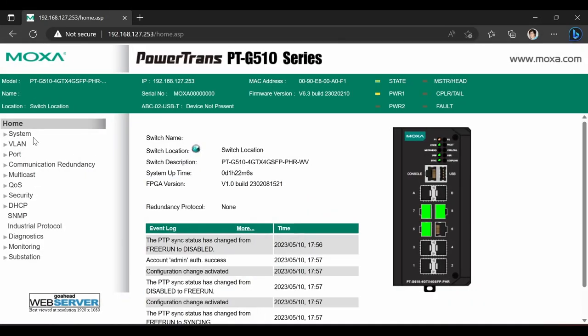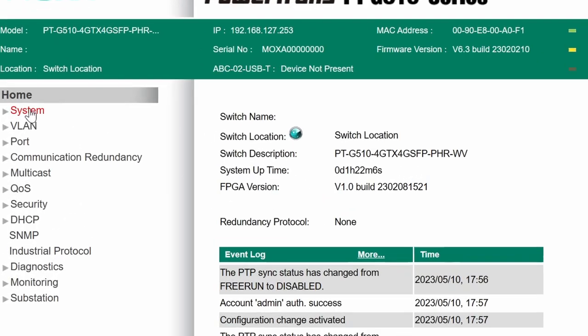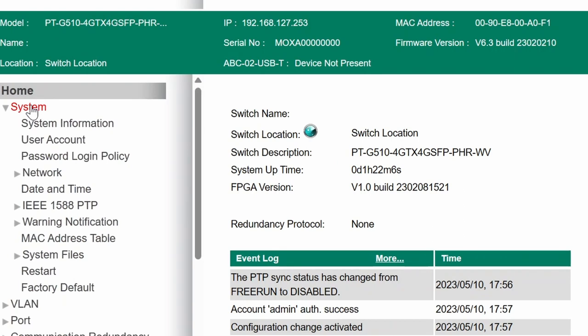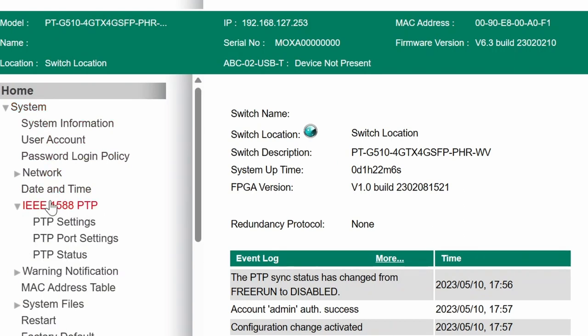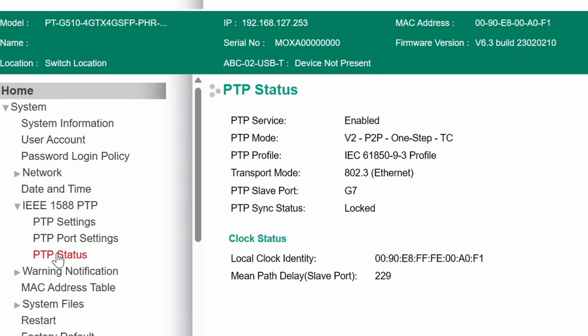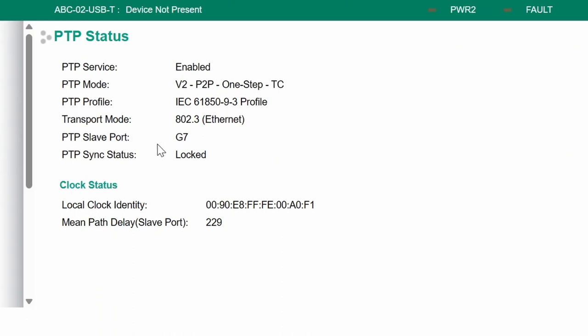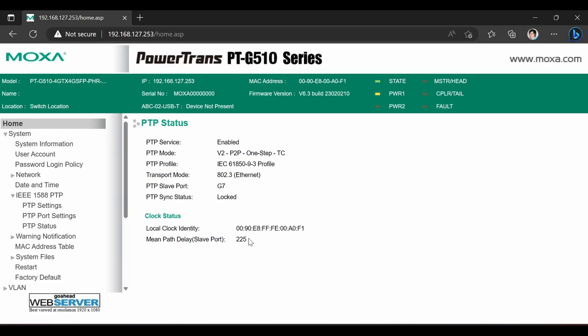Speaking of troubleshooting, if we go back to the web user interface, synchronization status can be observed on this page. This is the port which is connected to the current grandmaster, the state is locked, which is same as steady green sync LED, and we can also see a mean path delay in nanoseconds.